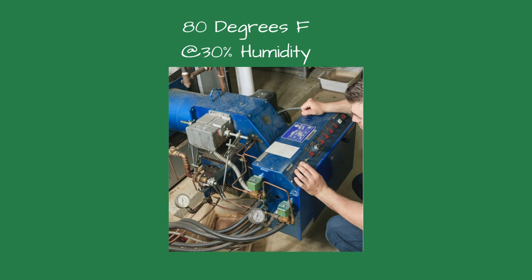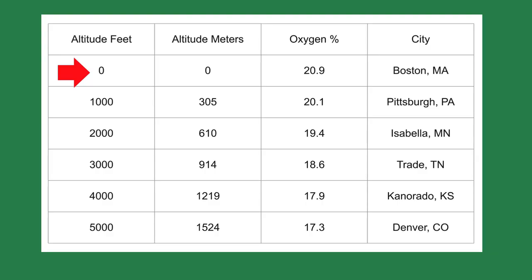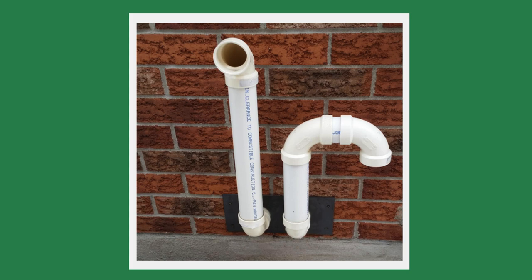Problems occur when the temperature or humidity changes. If you're in Boston, Massachusetts, you're at sea level and the oxygen percentage in dry air is about 20.9 percent. If you're in Denver, Colorado, the oxygen percentage is 17.3 percent — you would need 20 percent more air in Denver than you would in Boston.